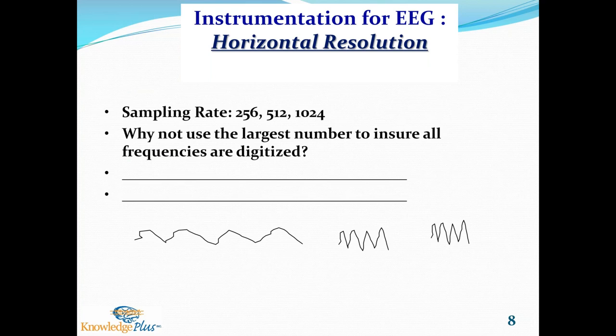Well, we're going to start today with horizontal resolution. On your instrument, you have a choice of sampling rates of 256, 512, or 1024. And with many things, we always think bigger is better, more is better, but that may not necessarily be true. So if we were to ask which of these three would best serve to give us beautiful EEG, you might be tempted to pick 1024, but we don't really want to pick a bigger number if we don't need it, because not only will it resolve brain waves, but it's also going to resolve noise. So we want to get a well-represented EEG. We don't want noise resolution.